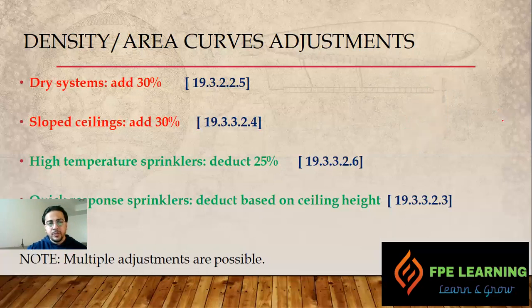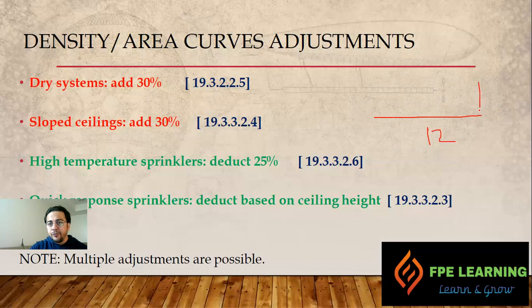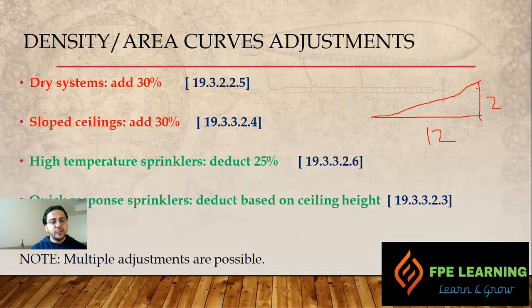For reference, the definition of a sloped ceiling is based on FM Global research: if the slope is more than 16.7 percent — that is, a rise of more than 2 units for every 12 units of horizontal run — it is considered a sloped ceiling and the 30 percent addition applies.